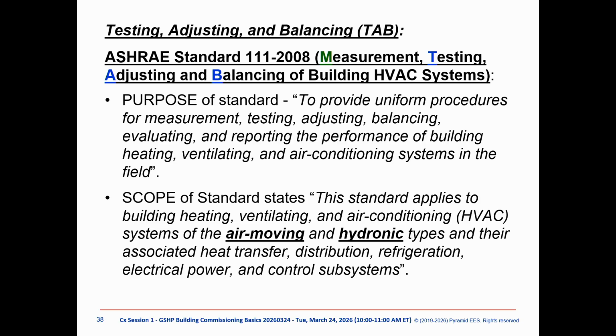Testing, adjusting, and balancing is TAB. I like the TAB contractor to be involved during the design process. What happens is that when the building is built, they give a call to the TAB contractor. No, that's not the way it's supposed to be. The TAB contractor needs to be involved up front to make sure the ports they need for temperatures and pressures are available and accessible to perform their duties.